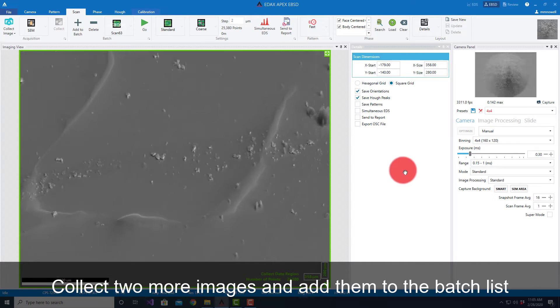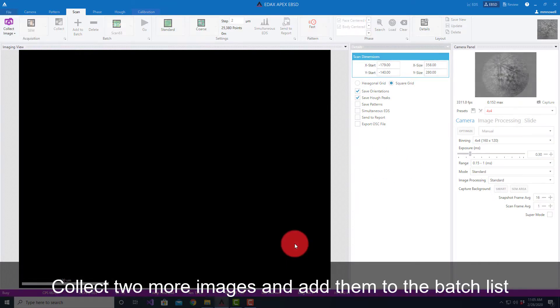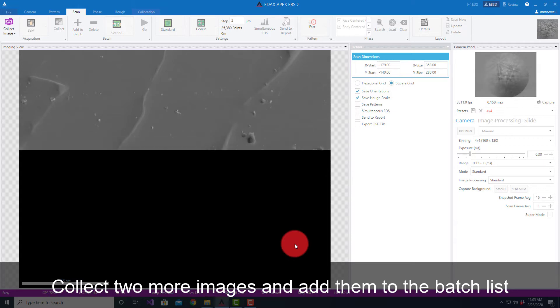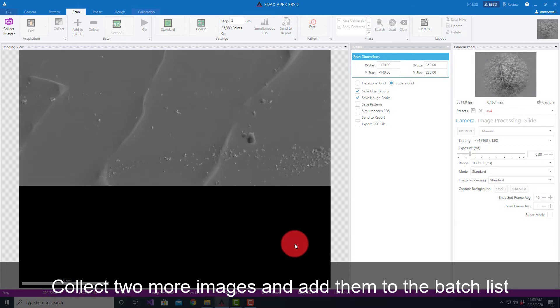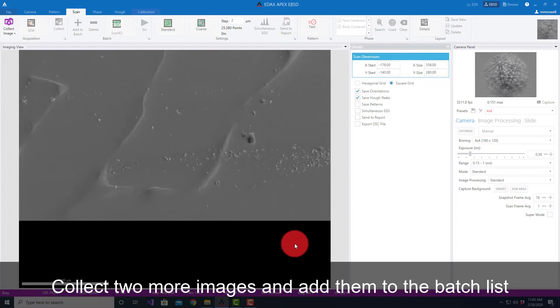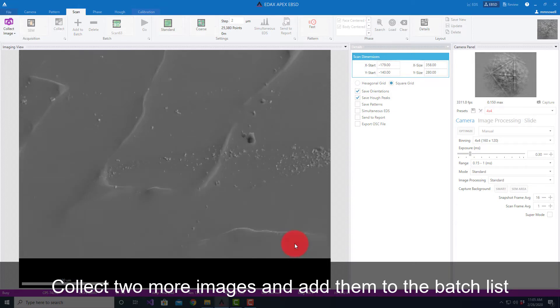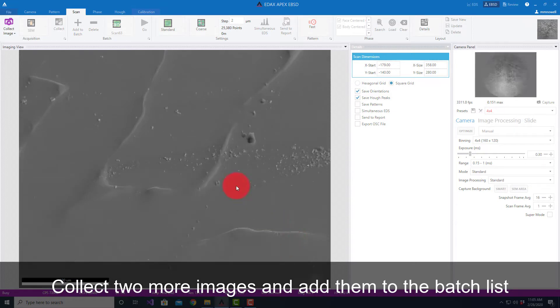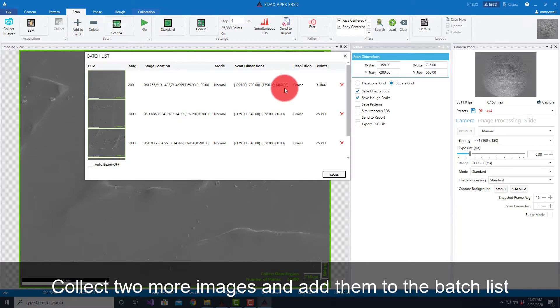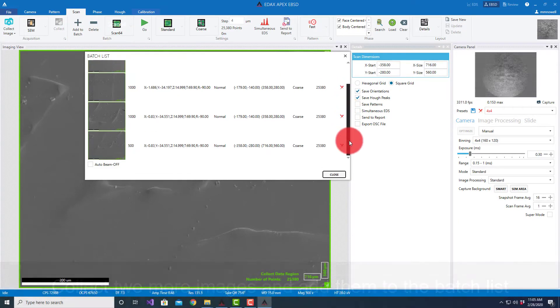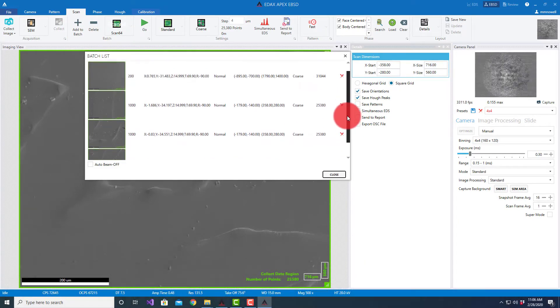At the same area, I could go out a factor of magnification to collect my image, so it can work at the same position without having to actually change the stage. Say Add to Batch. Now I have four scans in my batch here at different magnifications and different locations.